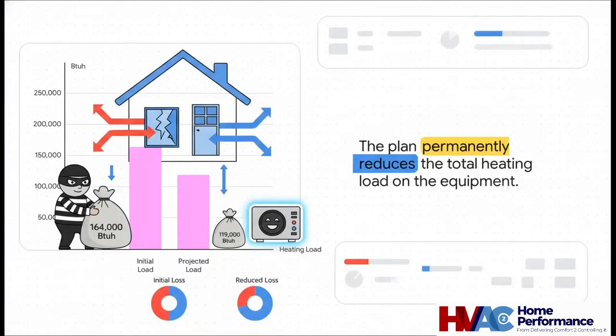And here is the result. This is the payoff for all that investigation. By implementing that plan, the total heating load required for the home plummeted from 164,321 BTU all the way down to a projected 119,382. That's a massive, permanent reduction in the work the equipment actually has to do.